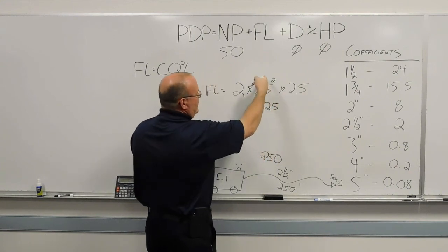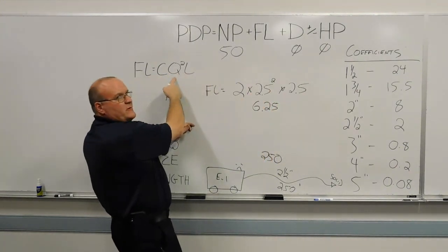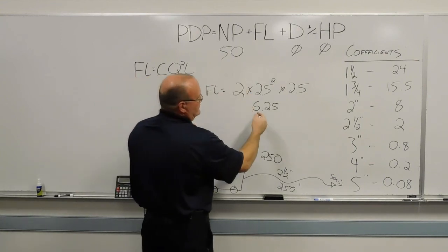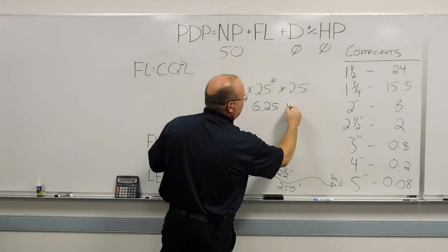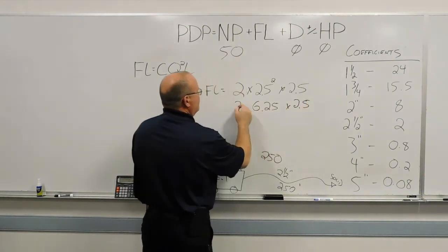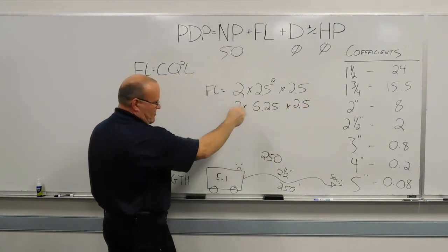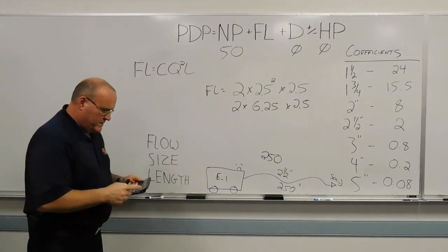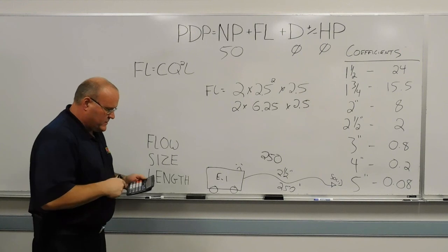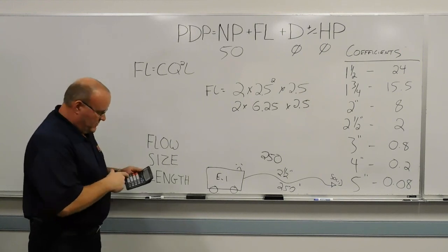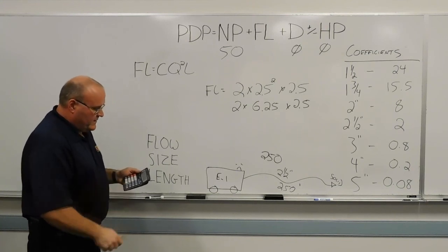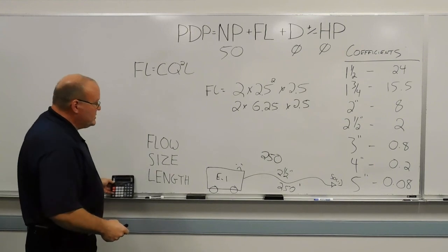So 2.5 squared, the Q squared part of this, 250 gallons a minute, divided by 100, 2.5. The square of that is 6.25. And then that remaining formula is what we use to get our friction loss. So 2 times 6.25 times 2.5, 31.25.